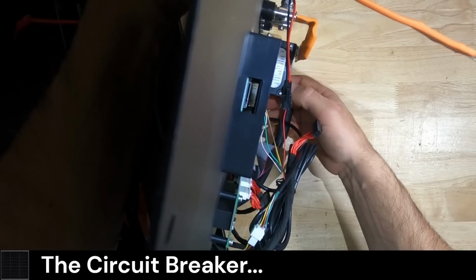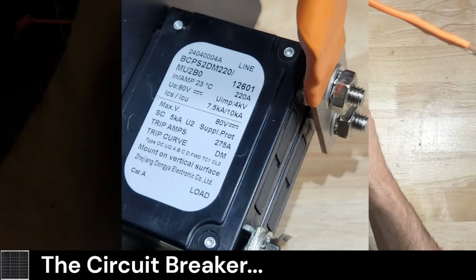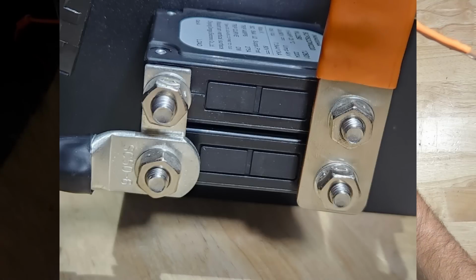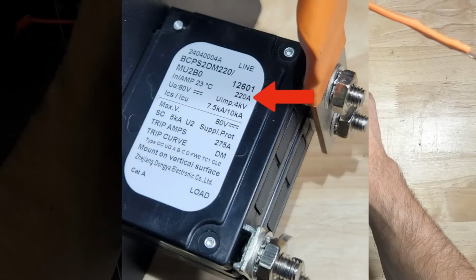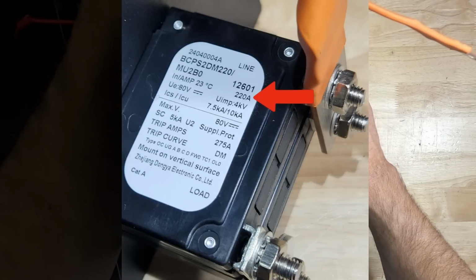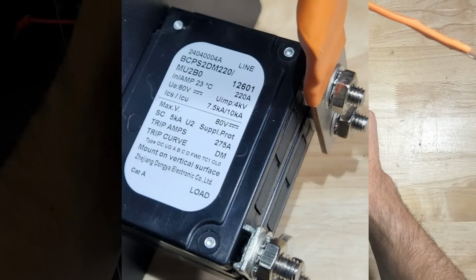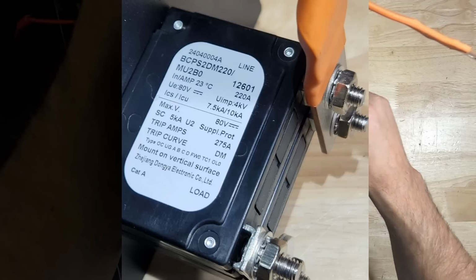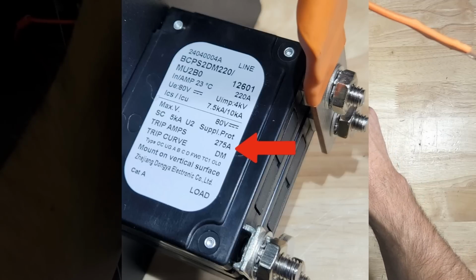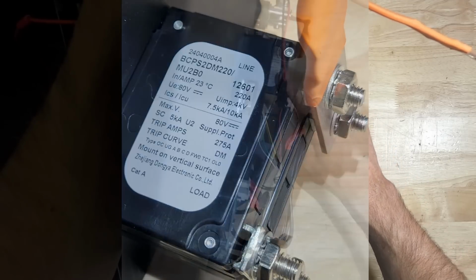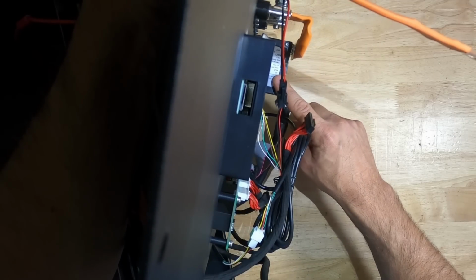Taking a look at the breaker here, it looks like they got a double pole breaker with bus bars spanning both poles, rated at 220 amps, 80% duty cycle. So what we have here is essentially 2 110 amp breakers coupled in parallel, with a 275 amp trip rating. So this is perfectly rated for the 200 amp BMS.